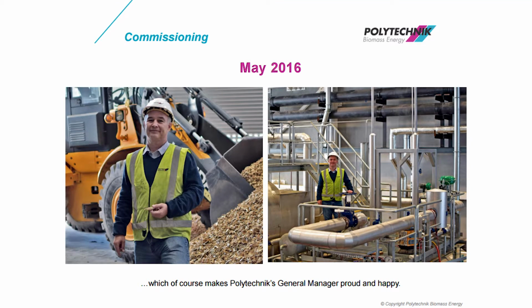So the outcome is we had a successful outcome. The plant runs unattended. The plant also automatically adjusts to the fuel that it's being fed. So if the moisture content goes up or down, or even the fuel changes, a high percentage of bark or a high percentage of whole fuel, the plant will automatically compensate. So there's no manual intervention.